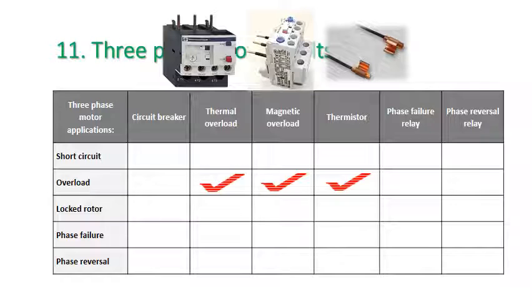The next fault is locked rotor, and really it presents the same issues as an overload. The rotor of the motor for some reason has been jammed and locked. It's not turning. There's no back EMF being produced in the motor, and so it heats up like there is an overload. So you can also tick all 3 of those for a locked rotor, and the same things that protect from overload.